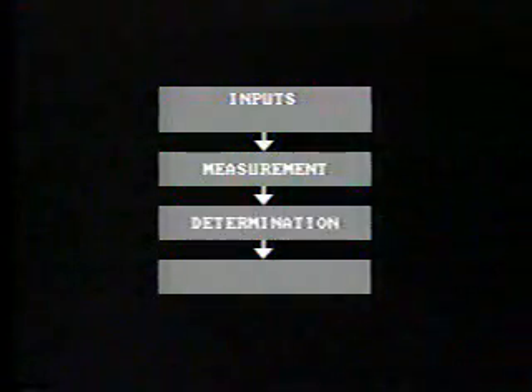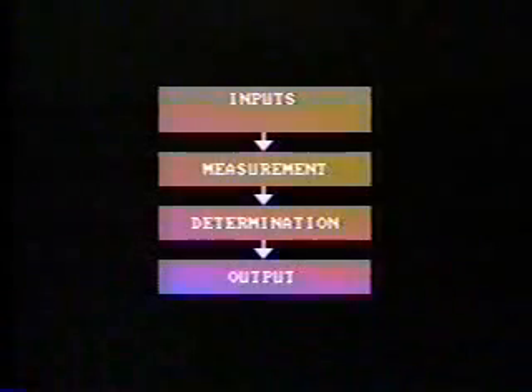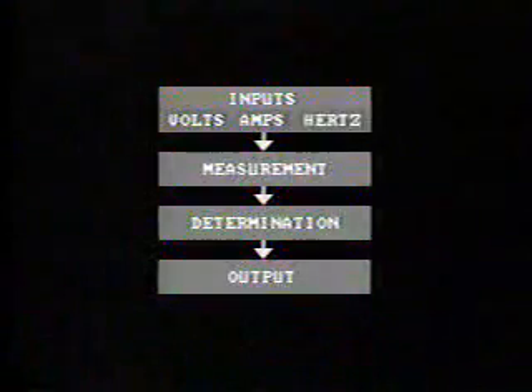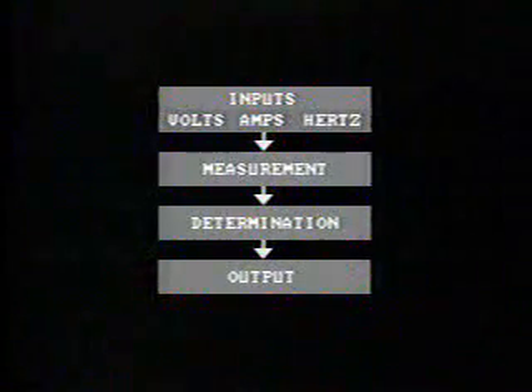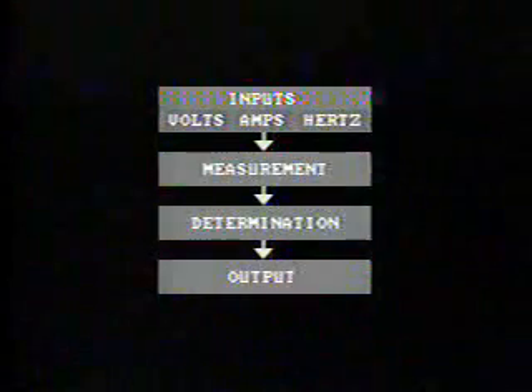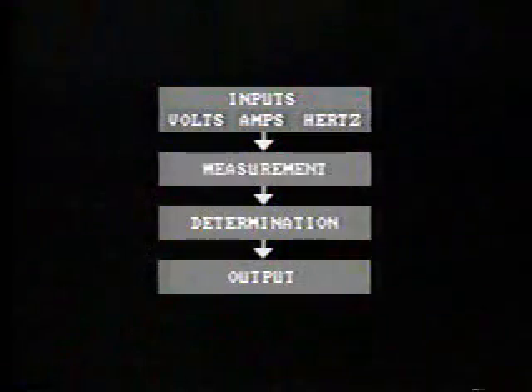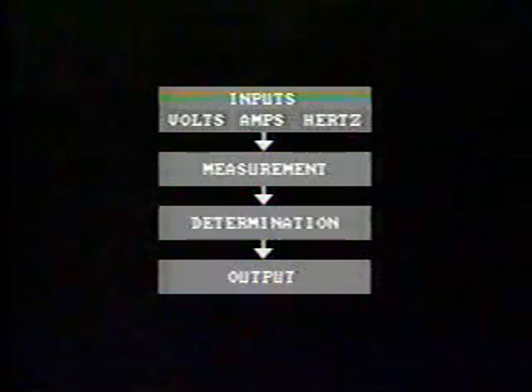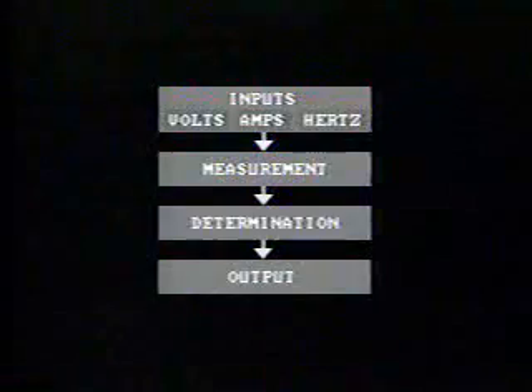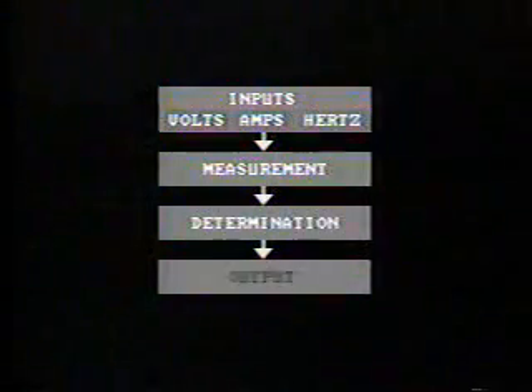As we all know, there are many different types of relays used in protective schemes. However, most relays follow the same logic pattern. That is, input, measurement, determination, and output. The input will represent current or voltage or frequency or perhaps other values which exist in the protected circuit at any instant in time. The relay measures these values and then determines if the circuit operating conditions are within normal parameters. Under normal operating conditions, output is zero, that is, a set of open or closed contacts at rest.